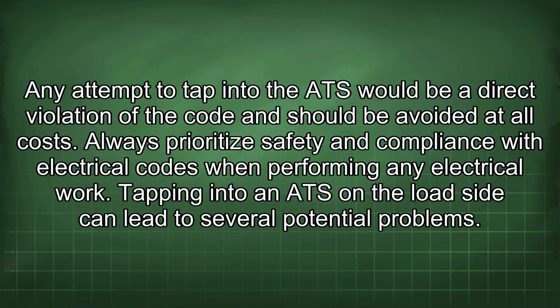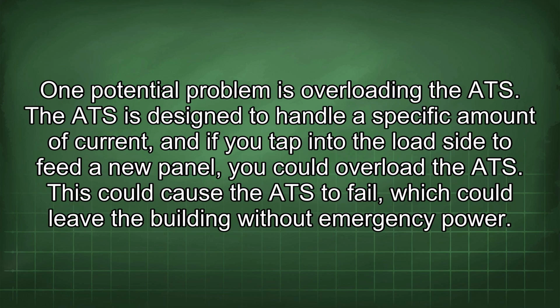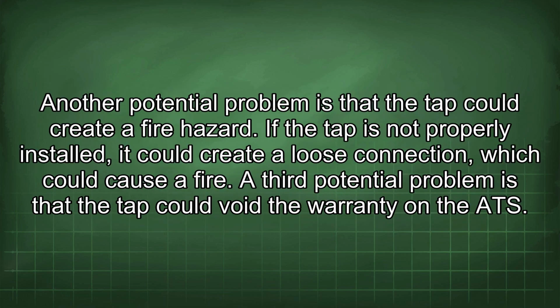Tapping into an ATS on the load side can lead to several potential problems. One potential problem is overloading the ATS. The ATS is designed to handle a specific amount of current, and if you tap into the load side to feed a new panel, you could overload the ATS. This could cause the ATS to fail, which could leave the building without emergency power. Another potential problem is that the tap could create a fire hazard. If the tap is not properly installed, it could create a loose connection, which could cause a fire.